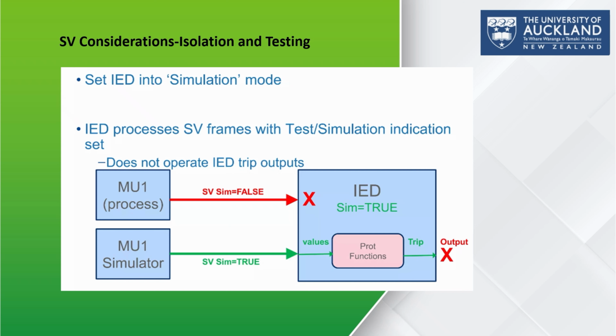Two types of sample value sources are shown. The first one is MU1 process, which represents the real merging unit sending actual electrical measurements from the power system. These real sample value frames carry a flag SVSIM equal to false, meaning they are real live data. The second source is MU1 simulator, which sends artificial SV frames for testing. These frames are marked SVSIM equal to true, indicating that they are simulated data intended for testing the IEDs.